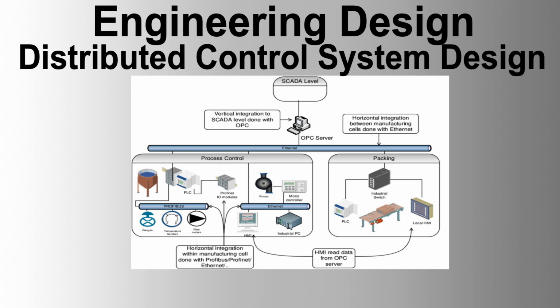3. Power distribution. The power distribution system must be designed to avoid single points of failure, ensuring continuous operation of the DCS. Protective devices must be coordinated to prevent a single electrical fault from causing multiple failures. Power distribution panels should include circuit breakers and surge protection devices to safeguard the DCS components. 4. Power supply monitoring. The DCS must include monitoring features to continuously check the status and health of the power supplies. Alarms must be generated for any power supply faults, including voltage irregularities, overload conditions, and UPS battery status. Power supply status must be integrated into the DCS operator interface for real-time monitoring and diagnostics.